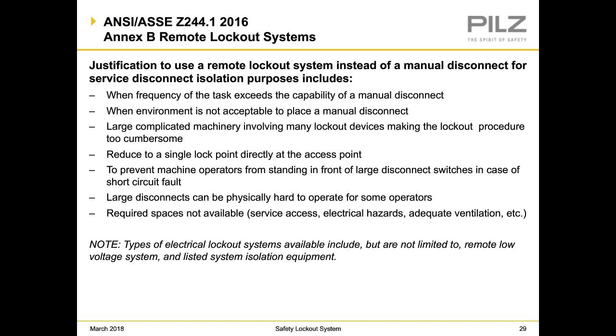at the access point, to prevent machine operators from standing in front of large disconnect switches in case of short circuit fault. Again, that's where the arc flash fault could happen and arc flash gear may be required and what have you. This takes that away. As well, large disconnects can be physically hard to operate for some operators. I've heard this on more than one occasion.